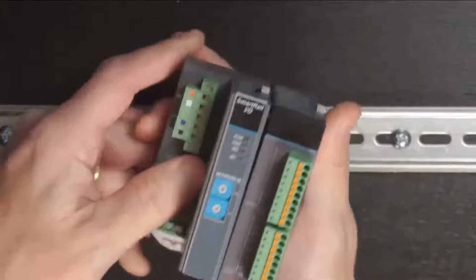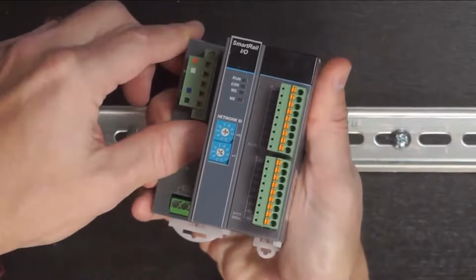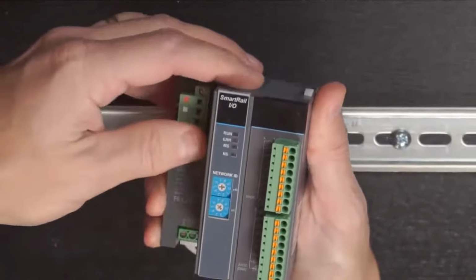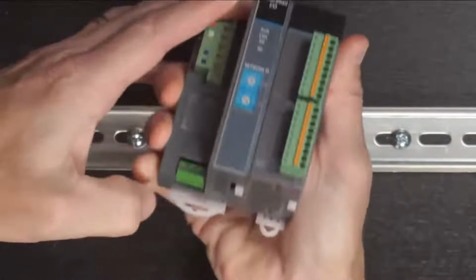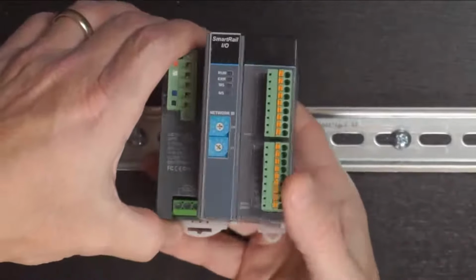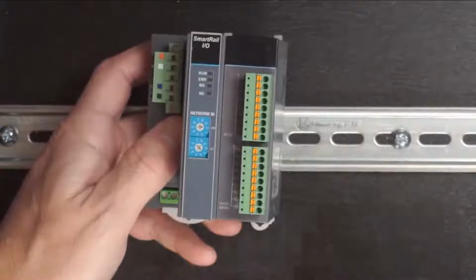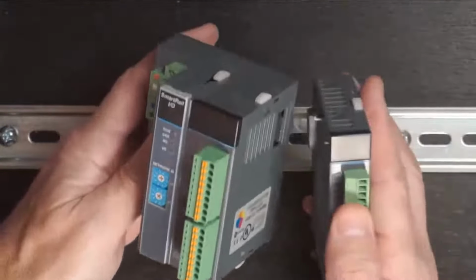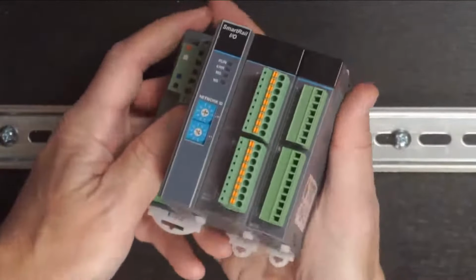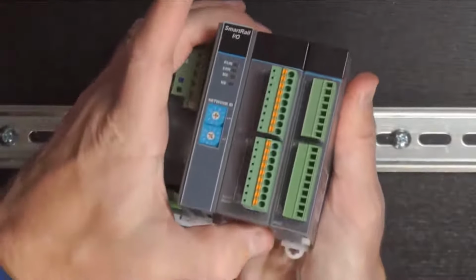The key really, besides just putting them together, is to squeeze. Okay, you don't have to squeeze super hard, but you should squeeze. That'll keep things nice and seated, where we can latch at the top and the bottom in whatever order we want, and everything is nice and tight. And then we just do that one by one until we're done. So let's put one more module on here. Okay, same procedure. Making sure everything's open, installing the module, squeezing, and then latching top and bottom.